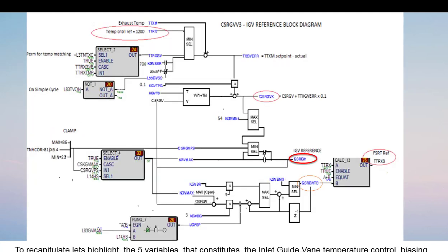To recapitulate, let's highlight the 5 variables that constitutes the inlet guide vane temperature control biasing. Number 1, TTRX, the temperature reference. It sets the error signal that opens or closes the inlet guide vane.